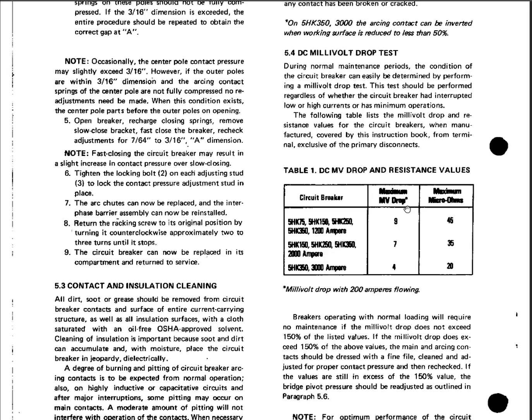So you have to understand the test that you're performing. This is a millivolt drop check, this is not a contact resistance, and it is usually going to be higher than your ohmic resistances, your pure resistance.